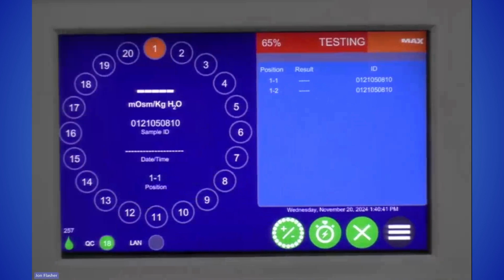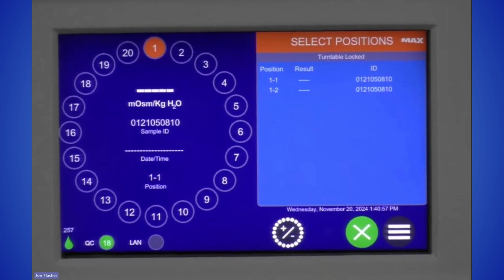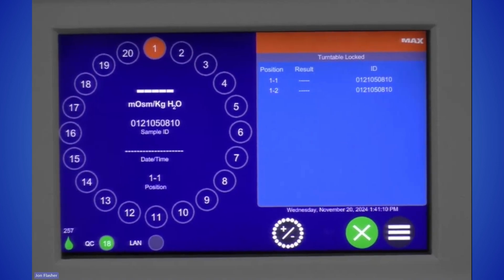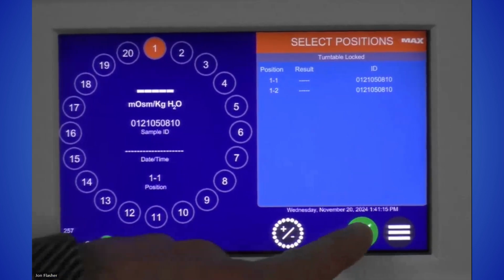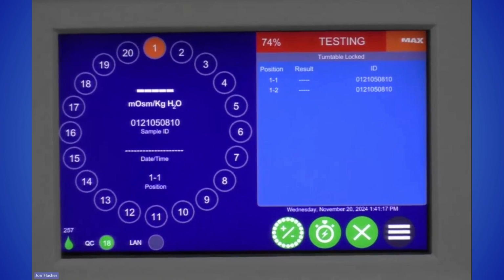Once it completes the test that it's currently running, it will go and scan that next one and add it to the queue. But let's say you get that stat test in from the ED and you need that result right away to inform that critical treatment. You can hit this little stopwatch with the lightning bolt, and a message on the top will pop up that says select positions. You just select a position on the turntable, scan it in, put it in that position, and then let it roll. It will prioritize your stat test over all of the other tests that are waiting in the queue to be tested in your turntable. So a really cool feature on the OsmoPRO MAX.